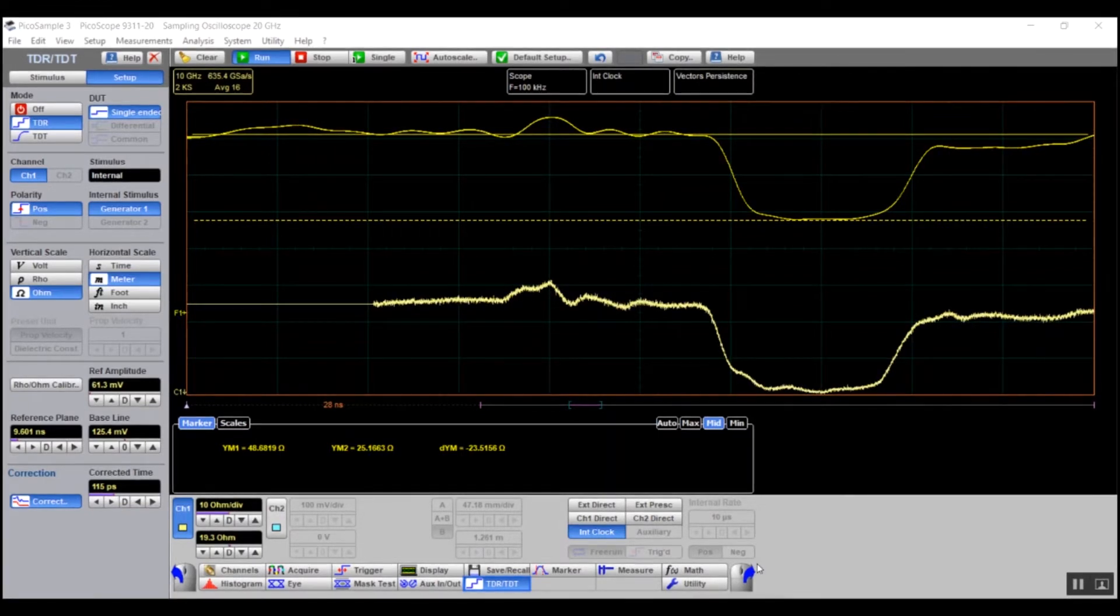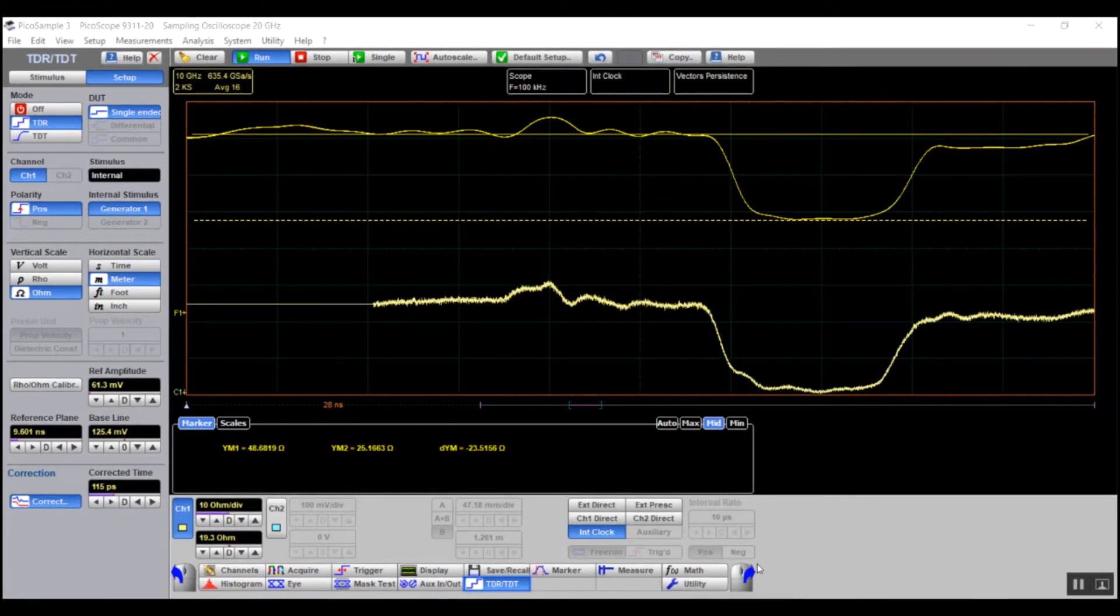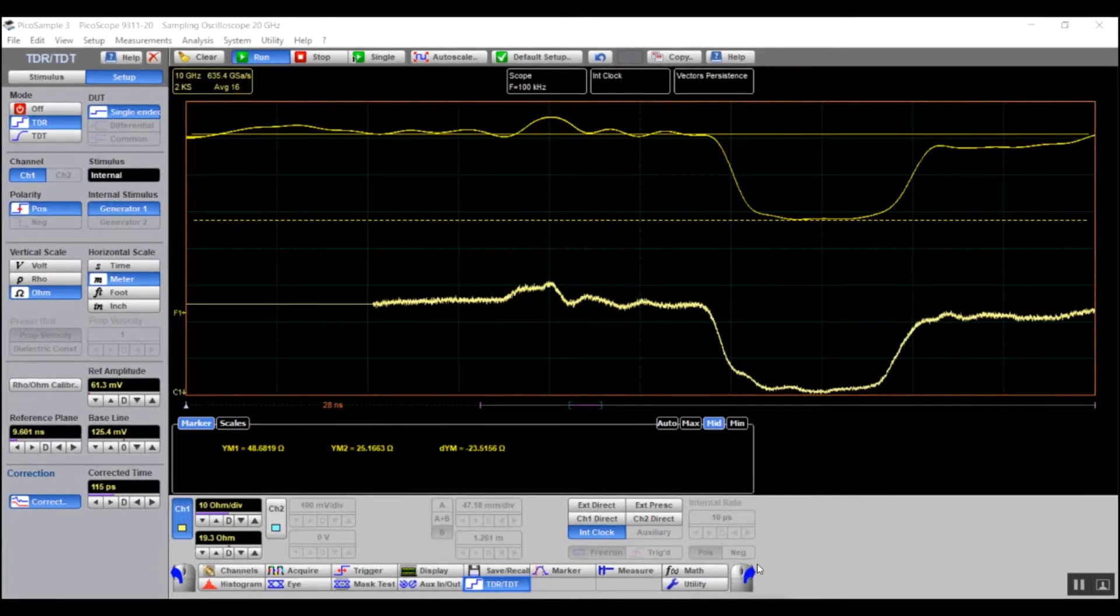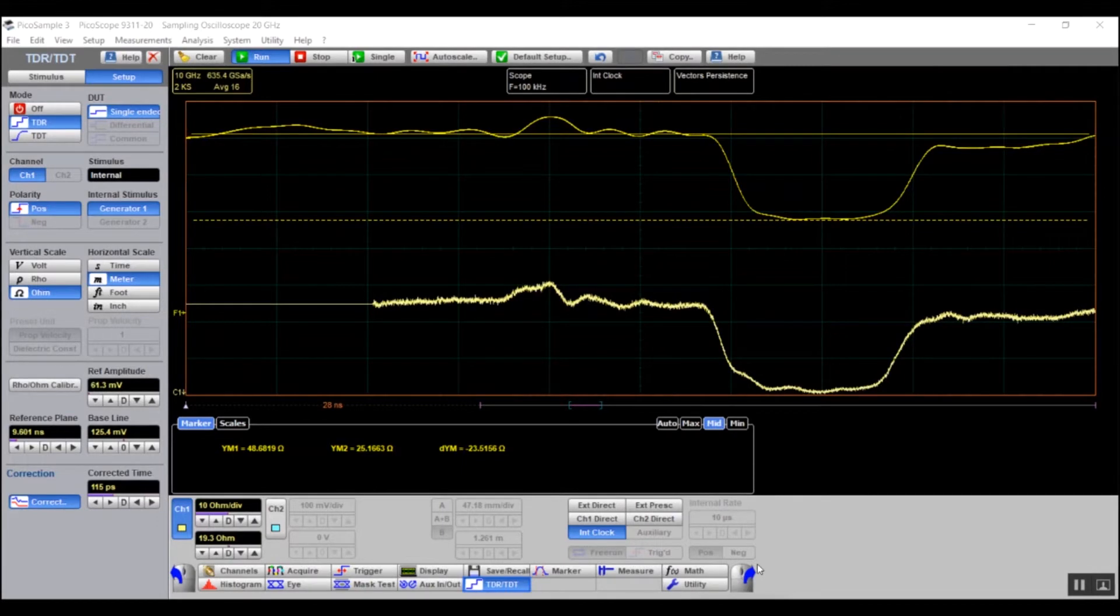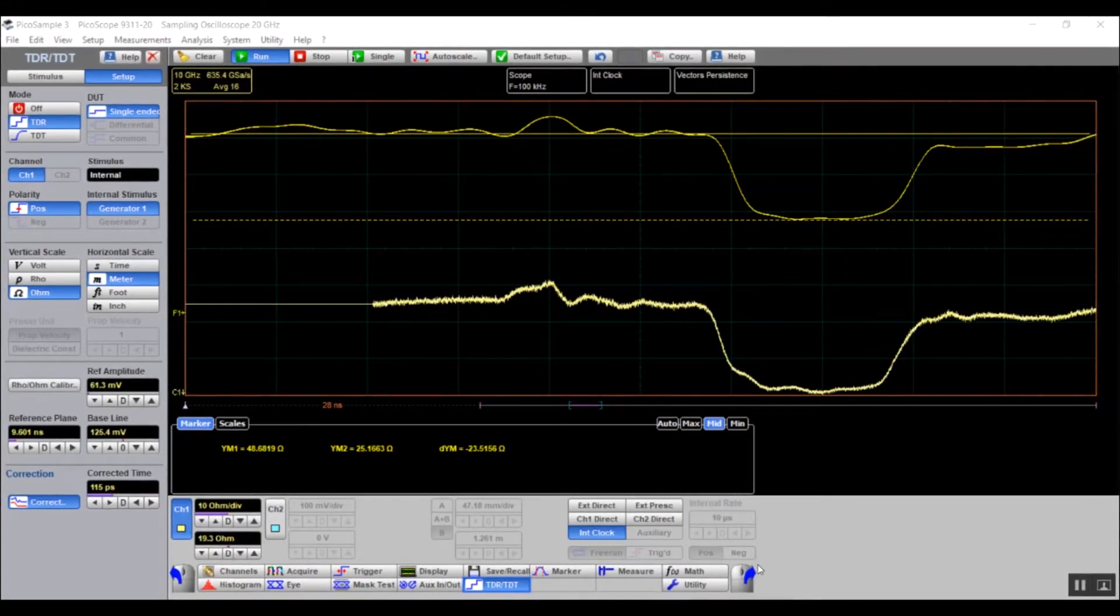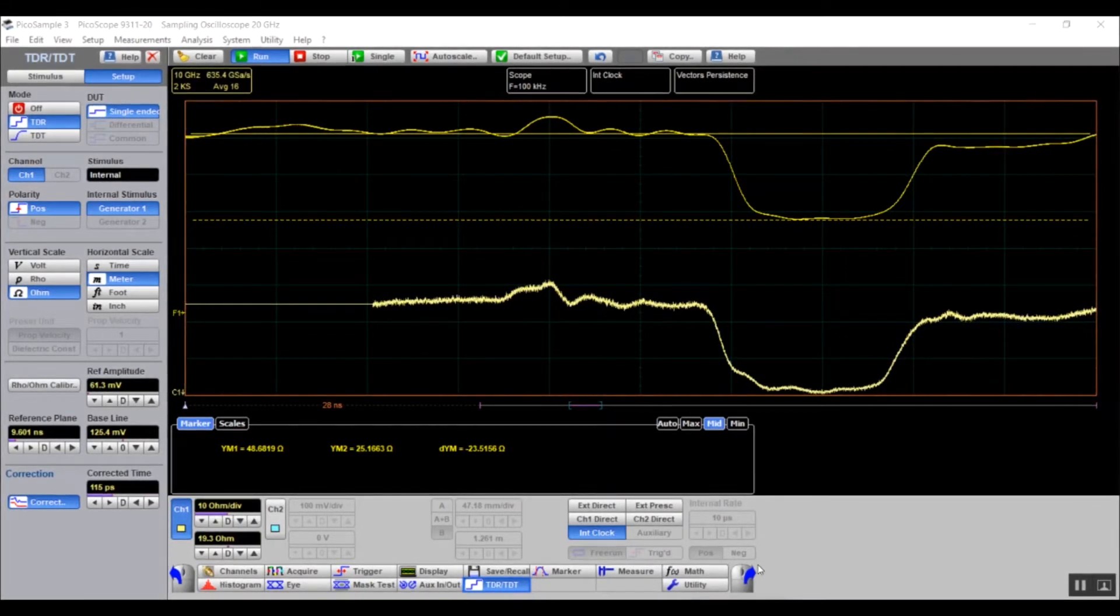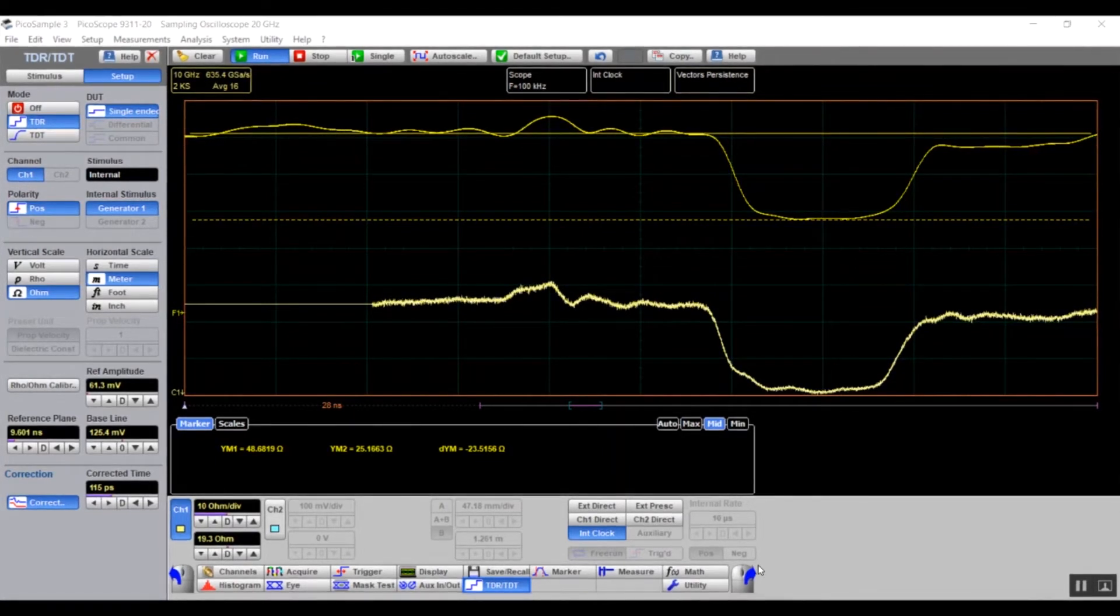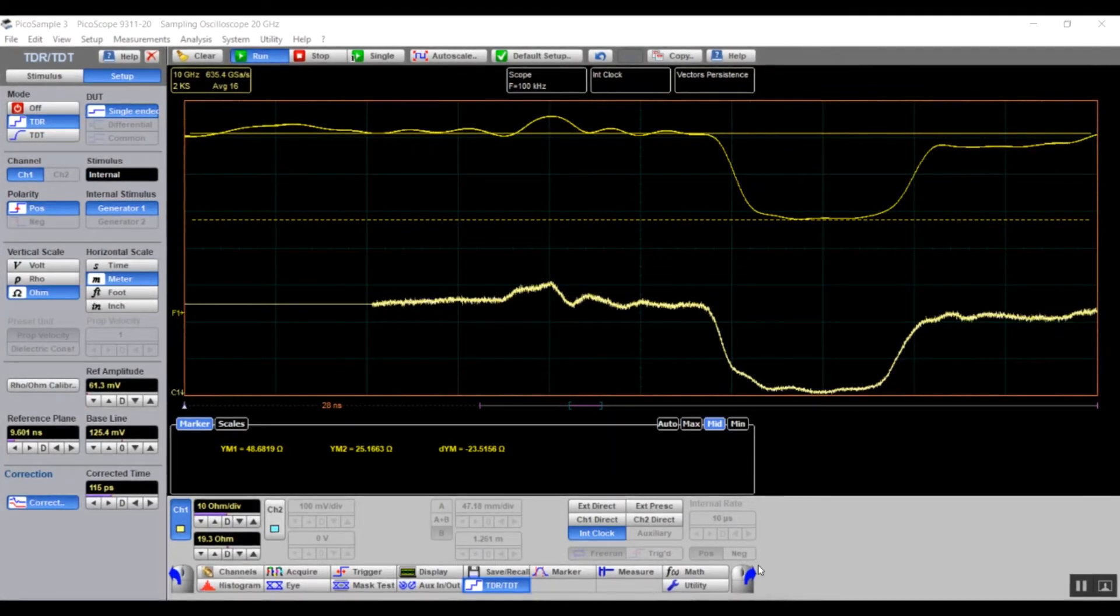The instrument provides a fast gain calibration and correction which easily allows you to change the rise time of the corrected step for TDR or TDT on each of the channels. By using correction, the results become more reliable, more repeatable and accurate.